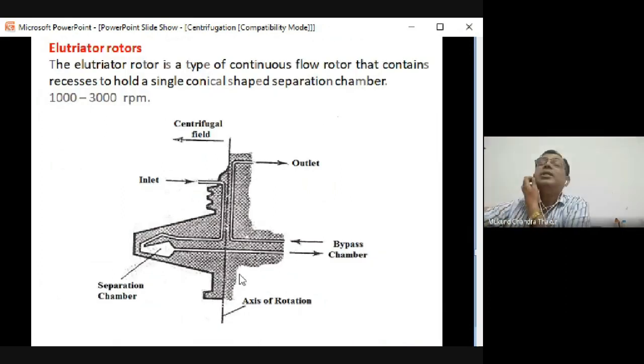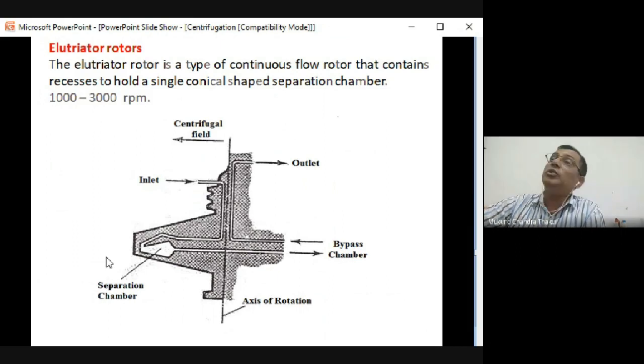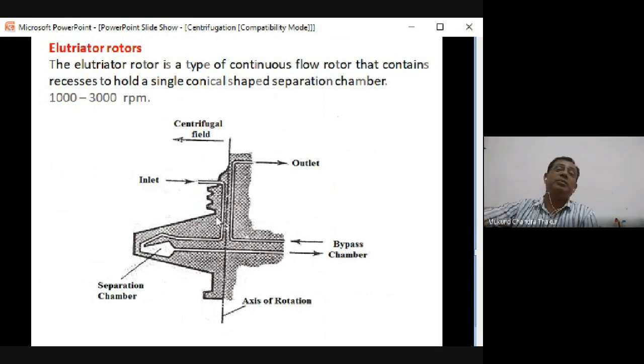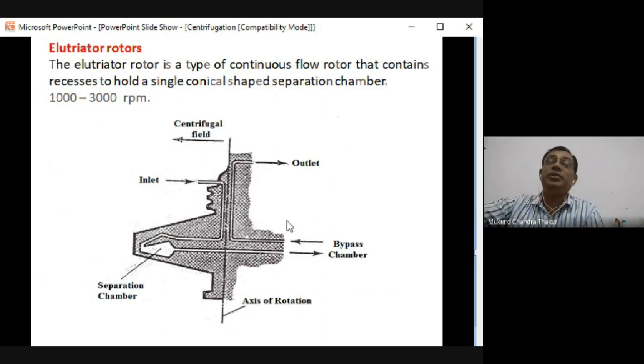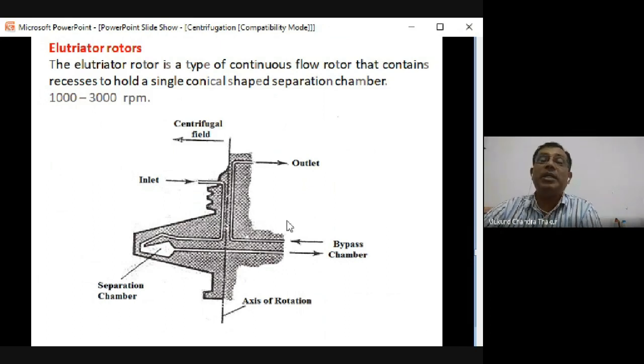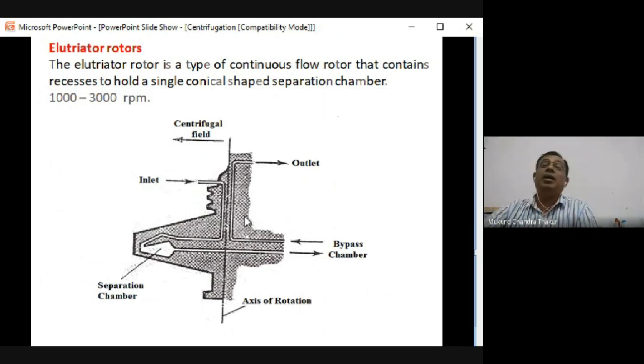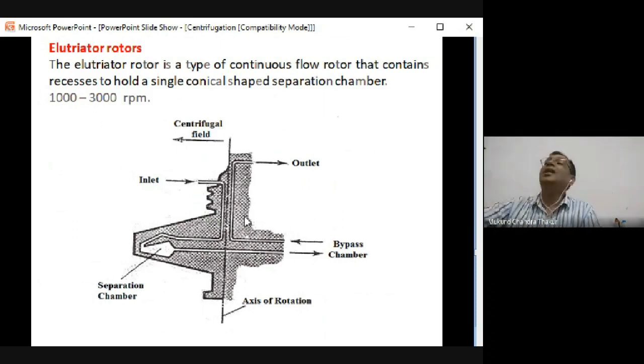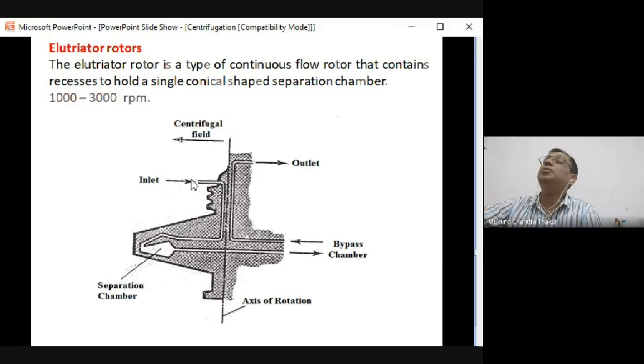The elutriator rotor operates in continuous mode, mainly used in industry with large-scale fermenters of hundreds or thousands of liters. Operating in batch mode with such volumes would introduce contamination problems. The typical chamber design allows sample to flow in, heavier particles settle at one side, lighter at the other, and fractions are pushed out and collected sequentially.